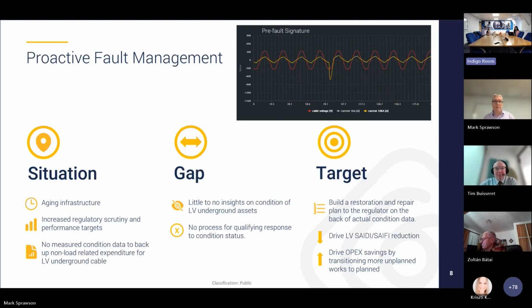The diagram at the top of this slide shows a similar signature, a nice sinusoidal voltage waveform, and a similar spike in the current shown in yellow. However, where last slide it was 7,000 amps and the circuit tripped, in this case it's 700 amps. You see it then goes back to the nice waveform of the current going through. There is no trip here, no one has gone off supply, everything is still okay on that network.